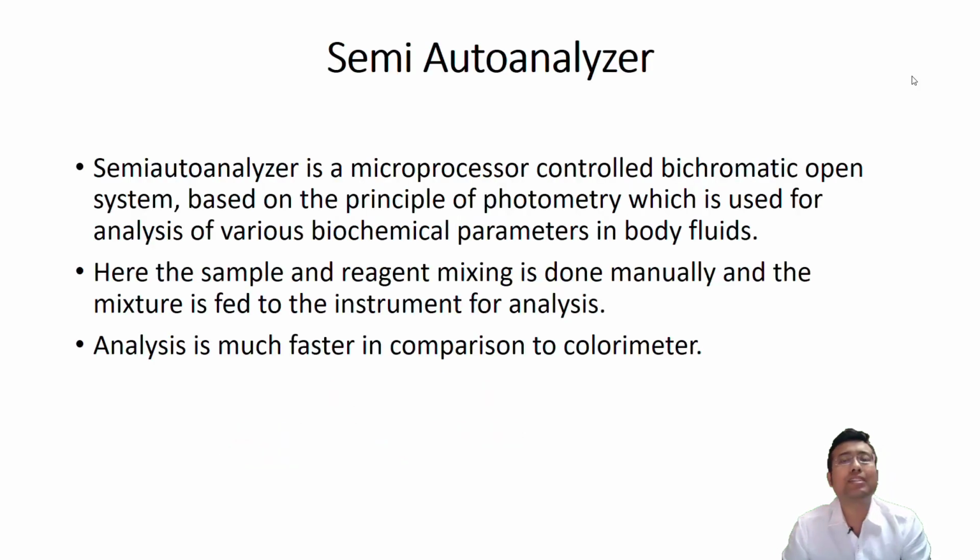So, first understand what we mean by semi-auto analyzer. You may be asked to define a semi-auto analyzer in your theory paper, or you may be simply asked what this instrument is. Let's see in detail what scientific terminology we can use for semi-auto analyzer. It's actually a microprocessor controlled bichromatic open system. Now all these terms are important.